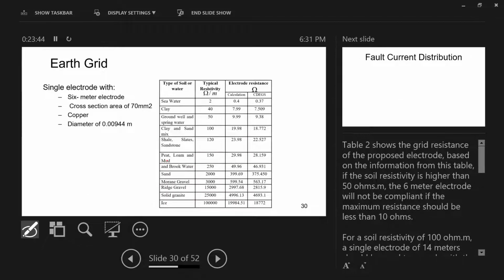And look, guys, I ran a couple of scenarios based on a hand calculation, based on CDEGS. By the way, CDEGS is one of the most powerful software packages in earthing systems. We installed a 6-meter electrode. The cross-section area is 70 square mm. And look, guys, the resistance for different values. If you have clay, your resistance is 7.99. If you have gravel, look at your resistance: 2,000, 5,000. So depending on your system, it's very important to obtain the soil resistivity, then determine the resistance.